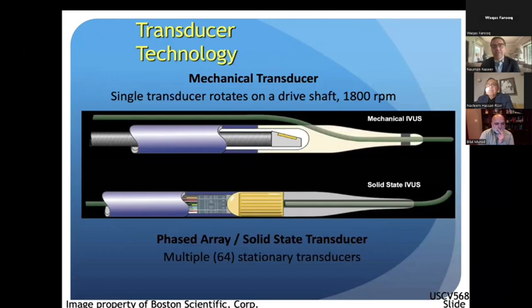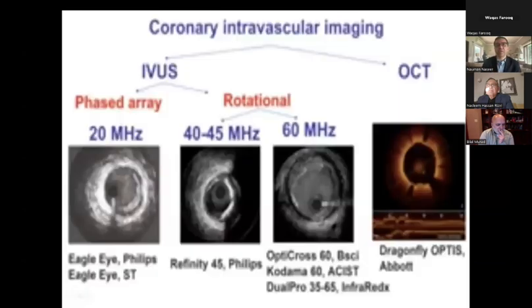We have two, Boston Scientific and Volcano, which is now taken over by Philips. So the Boston Scientific is a single transducer which rotates like the lighthouse effect on a drive shaft at 1800 RPMs. And the phased array solid state transducers is multiple 64 stationary transducers which emit the ultrasound waves. Now this is phased array. It does not have as high frequency as the rotational catheters. So Eagle Eye, which we have over here, this is 20 megahertz typically, and you can get on rotational catheters 40, 45, and with some of the other rotational catheters up to 60 megahertz frequency with a better resolution.